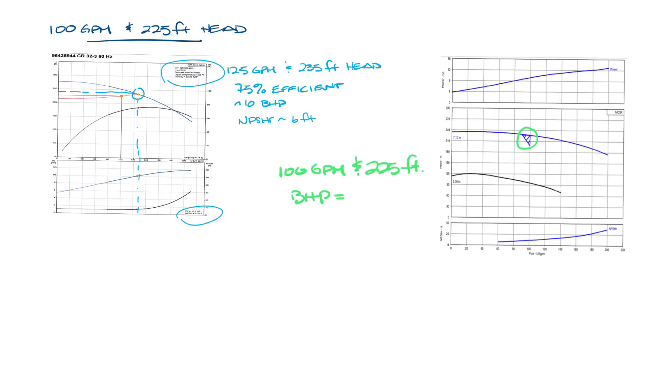The brake horsepower is about 9, and the NPSHR is about 11 feet. It doesn't show the efficiency, but I know from the selection it was about 62%. Okay, so let's move this over and just put these in a table.